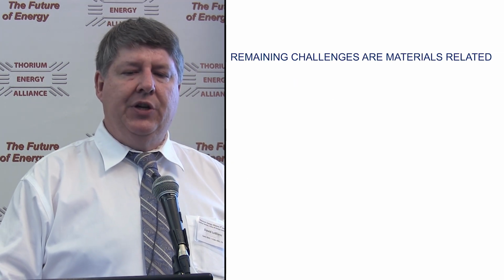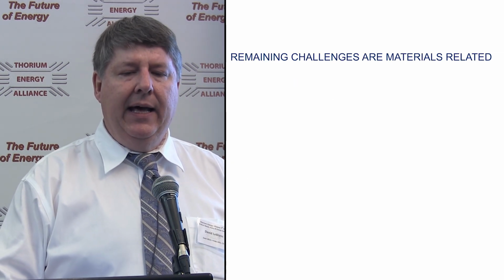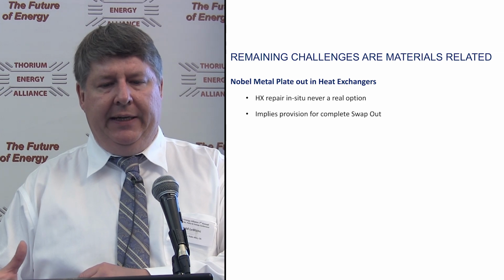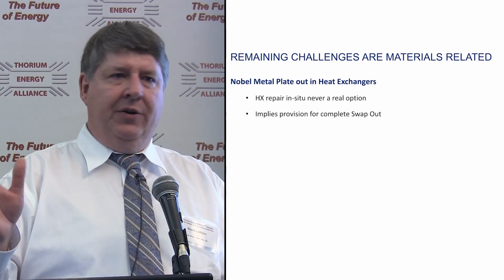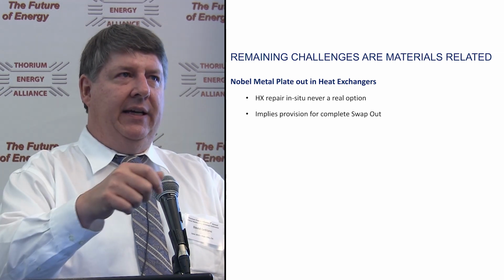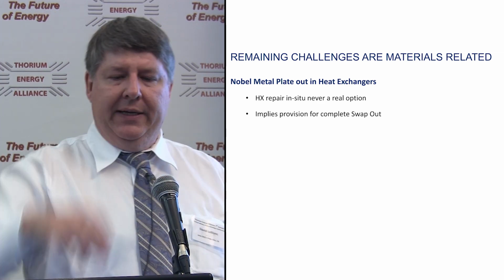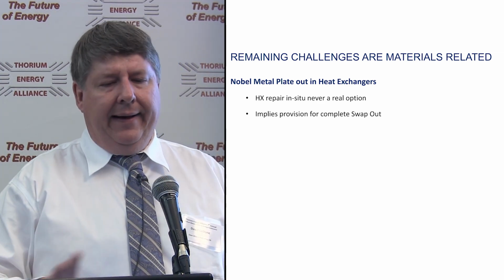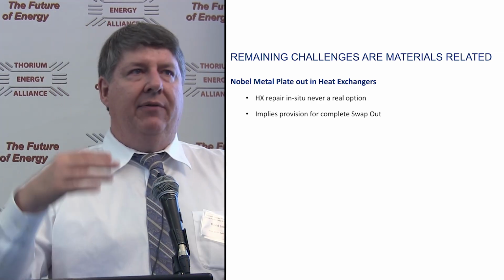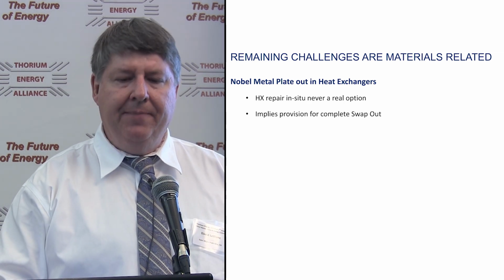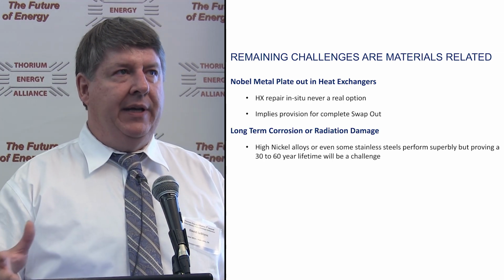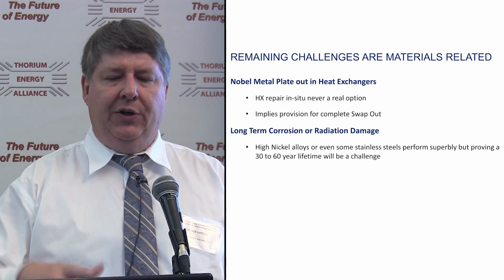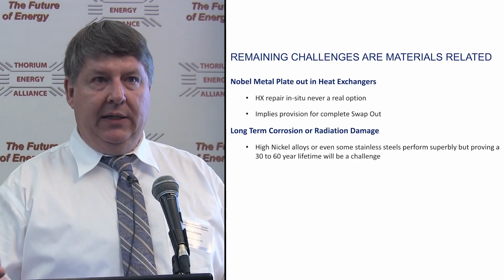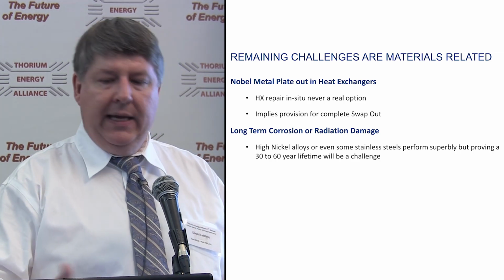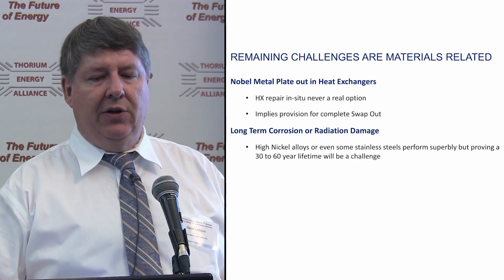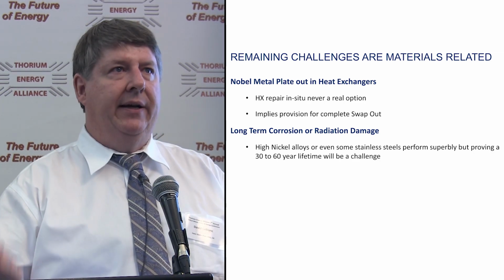The remaining challenges, I'd say, are really materials related. Noble metals tend to plate out in heat exchangers. We always knew you're not going to talk about going in and fixing a heat exchanger. If you have a problem, you're replacing the entire tube bundle. A little tricky if they dry out, if there's a heat source there. Long-term corrosion and radiation damage of the metals we use: high nickel alloys, Hastelloys, even some stainless steels perform superbly, but proving a 30 to 60 year lifetime is going to be a challenge to the regulator, to the investor, etc.